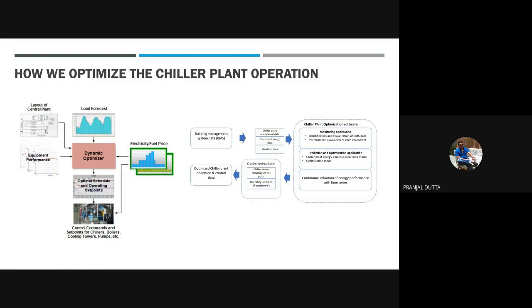So all the operating parameters need to be input in the particular layout of the chiller plant. Then equipment performance needs to be inputted in this dynamic optimizer. Equipment performance, you have a different model for all the different equipment. For chillers there is a different method of calculating the coefficients, for pumps there is a different way of calculating the coefficients, and for cooling towers there is a different way of calculating the coefficients. From there, and later pricing and everything, it optimizes schedules and operating set points.